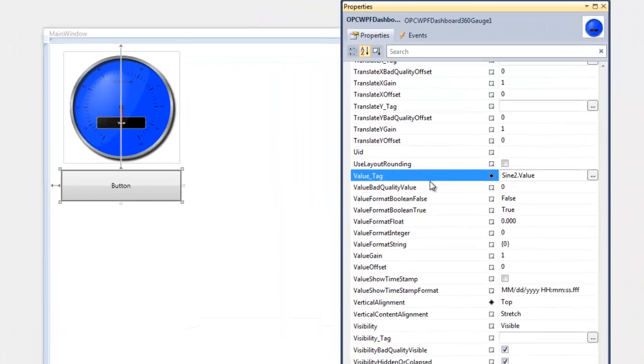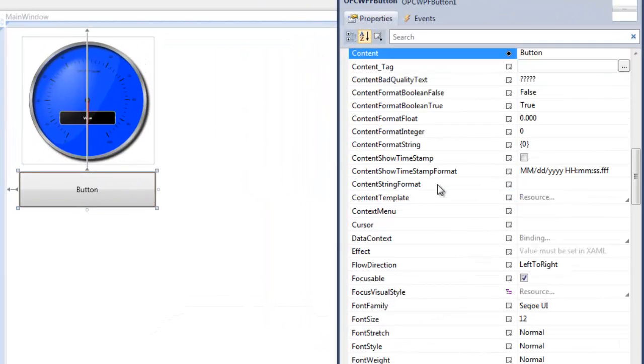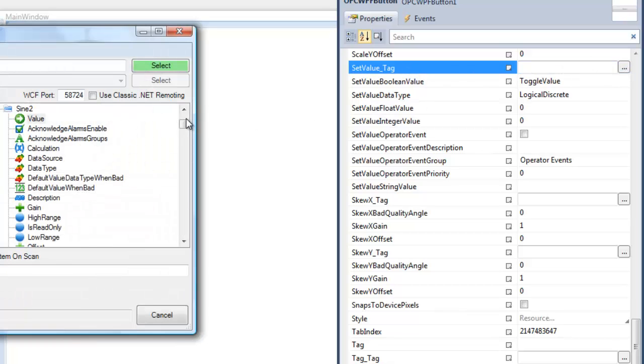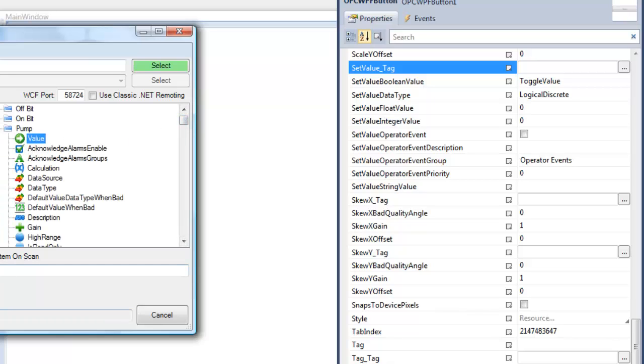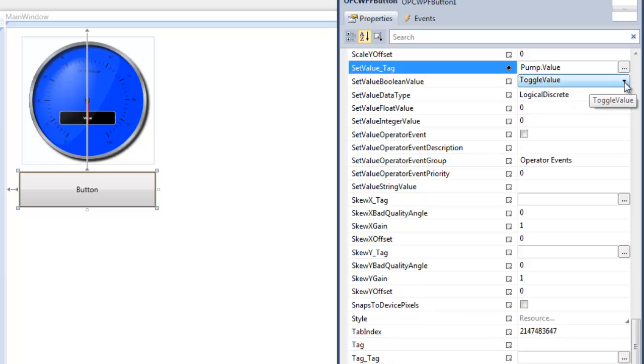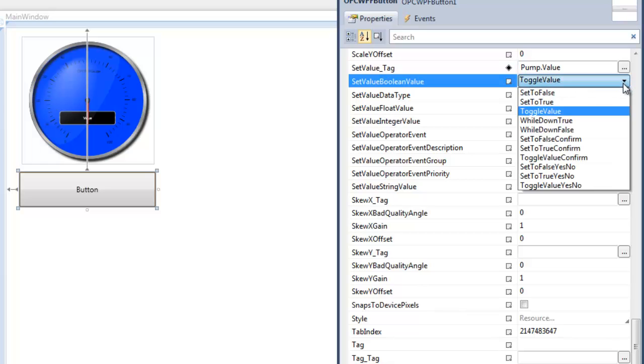Now let's use the OPC WPF Button control from the toolbox. With this button, we're going to change the state of a Boolean point — it could also be integer or floating point values. The button has a Set Value property. We'll browse and select the tag Pump, property Value — a Boolean point. For Booleans you can toggle (the default), set a specific value, or use while-down mode. You can also use confirmation dialogs. Other entry types include text entry with keypad or keyboard entry and numeric keypad entry, which are great for touch screen applications.